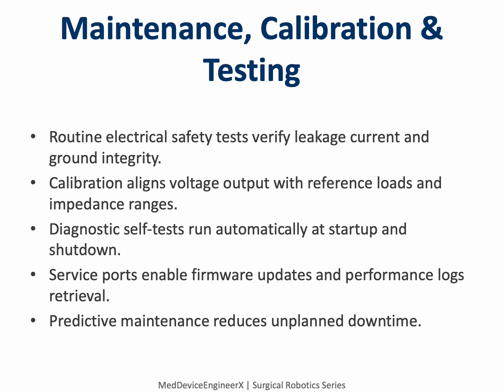Service ports on the tower allow firmware updates and data export for traceability. Predictive maintenance software analyzes usage cycles and activation counts to schedule service before any issue arises. Together, these practices ensure consistency and longevity, because in electrosurgery, reliability isn't optional. It's a foundation of safety and precision.